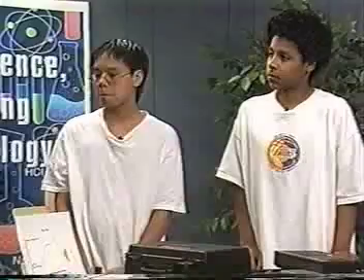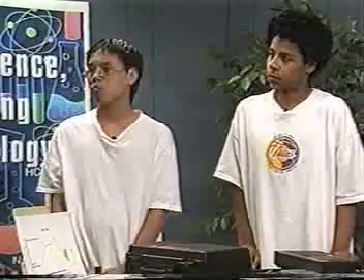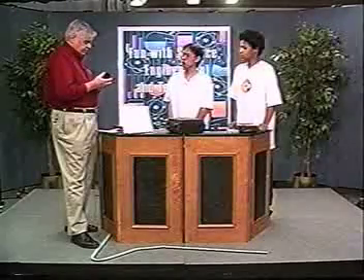Once a year, the meter itself and the little calibration unit are sent off to this lab, where they make sure it's putting out 114 dB of sound at 1,000 cycles, and that it's running right and approximates the response of your ear, that curve that we had here. On this particular one, it has to be done once a year.